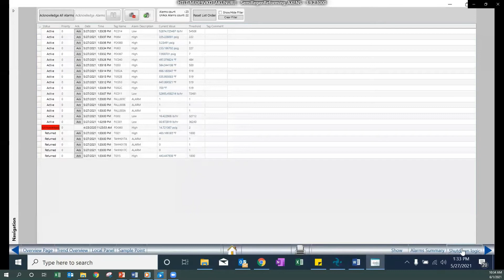Since the emergency shutdown valves have been tripped, the trainee would also visit the shutdown logic page, where the shutdown logic has already been implemented into the overall simulator. Here they can see which shutdown logic was tripped, and clearly we see this one, which alarm caused the trip, and the actions that it has performed. From here, the trainee can also reset the shutdown logic in order to reset the emergency shutdown valves to try and begin restarting the unit.